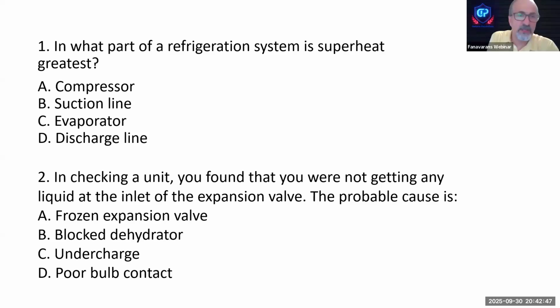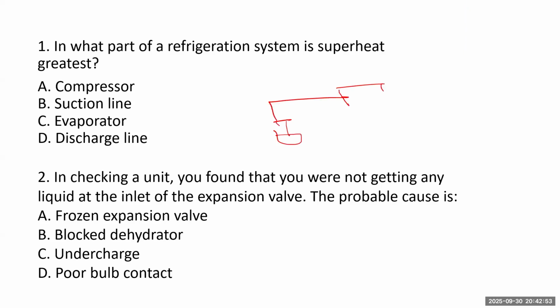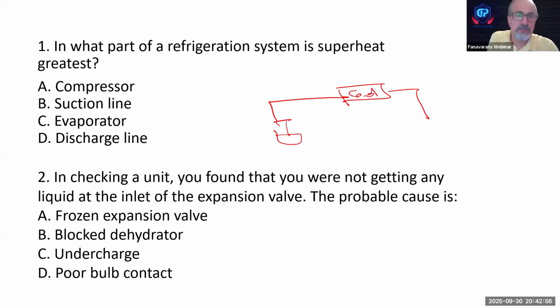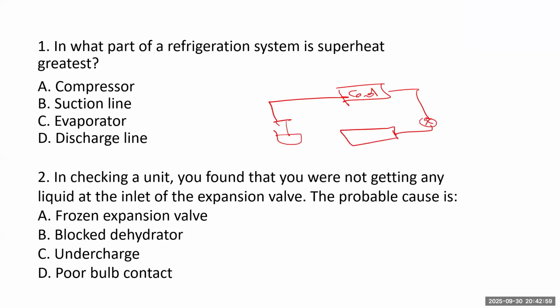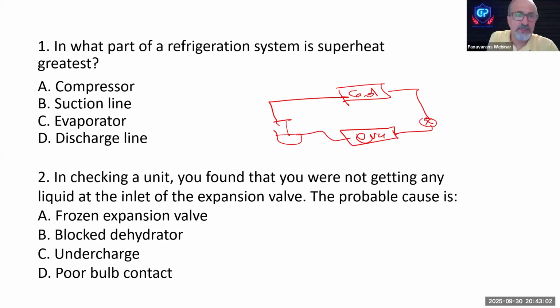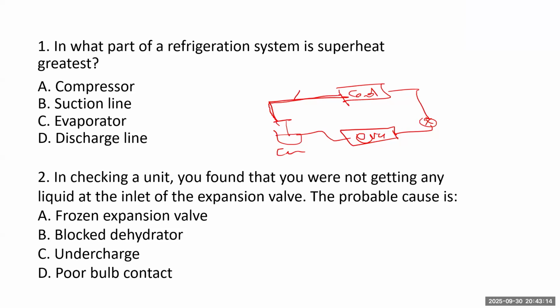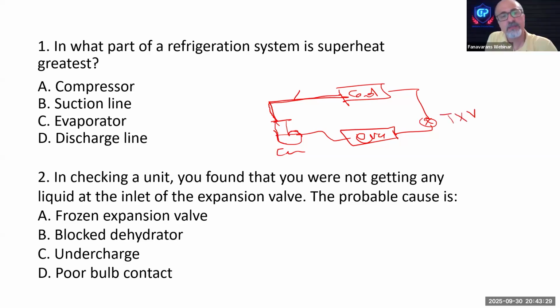So you know the refrigeration cycle has the compressor, discharge line, condenser, metering device, evaporator coil, and the suction line. This is the compressor. This is the discharge line, and when you measure the temperature at this line, it's hot and superheated. The compressor only compresses the gas, then the gas goes first to the discharge line, then to the condenser, and after that they all circle. You're right, the discharge line is pretty hot and it's the highest superheat.